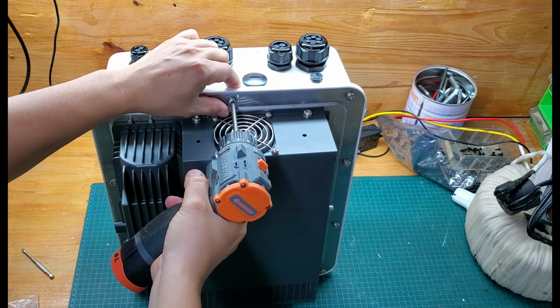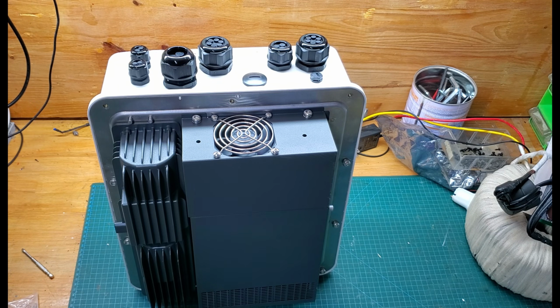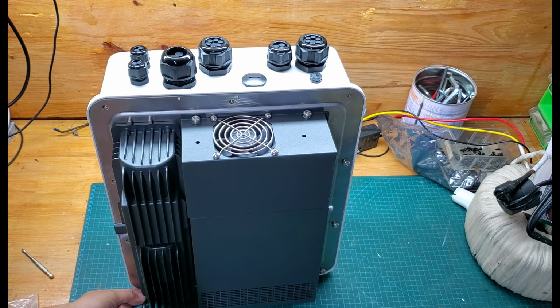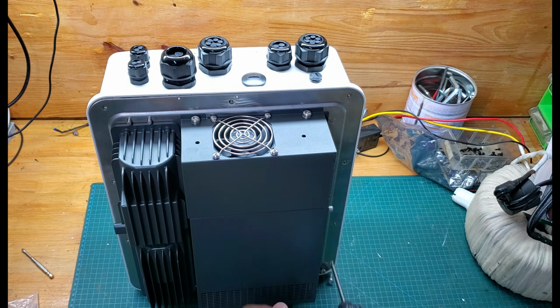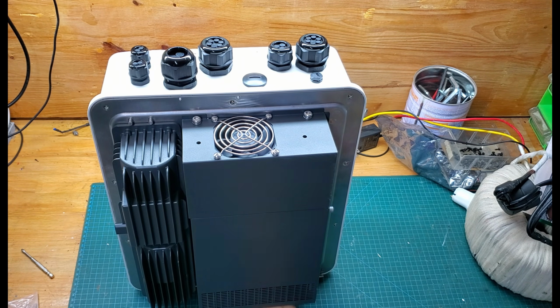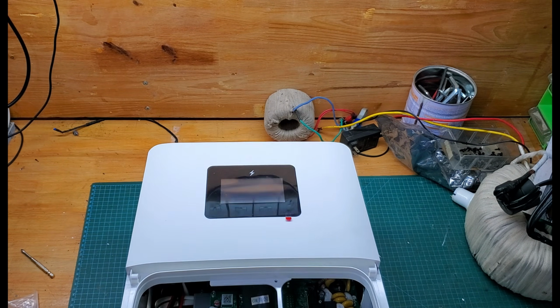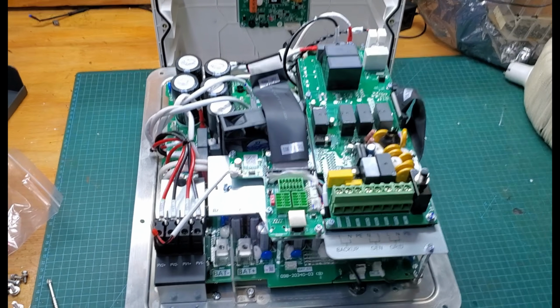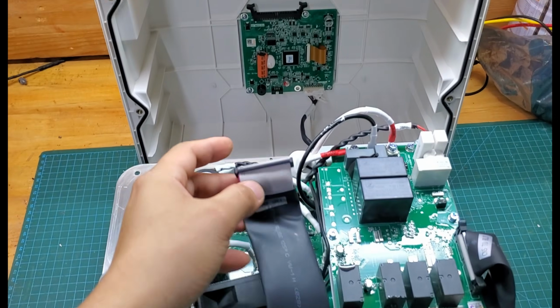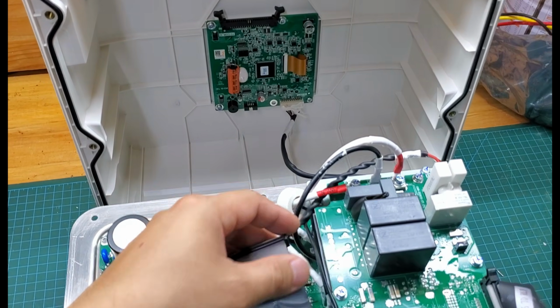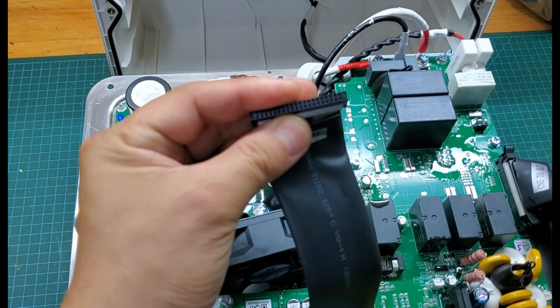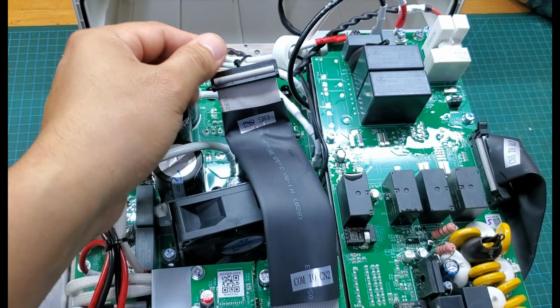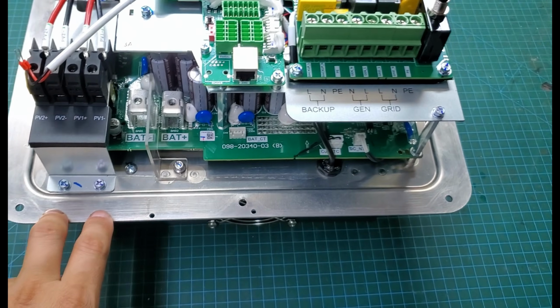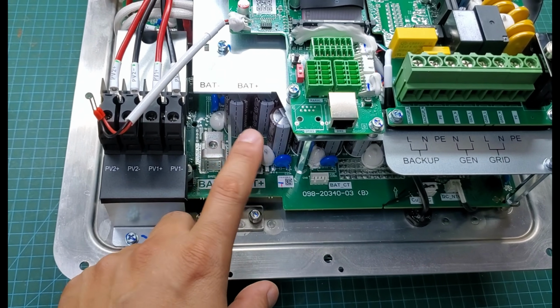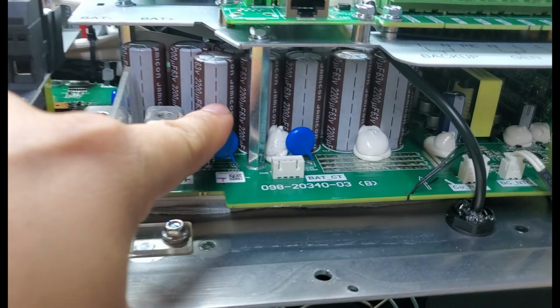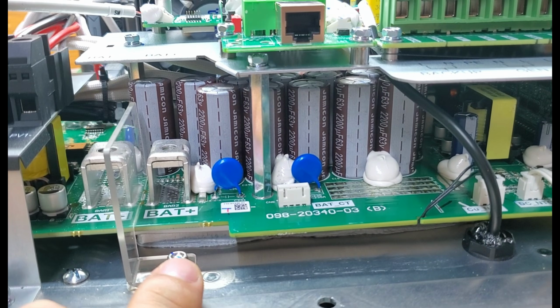Around the back, you can get a clearer look at the inverter's cooling system. The IGBTs, which generate a significant amount of heat during operation, are actively cooled using forced air from built-in fans to ensure stable and reliable performance. Here's a look inside the inverter. A large ribbon cable connects the display to the main board. You can also see the oversized battery terminals, designed to handle currents of hundreds of amps. Next to them are 12 capacitors from Jamicon, Taiwan, each rated at 2,200 microfarads and 63 volts, forming part of the power filtering stage.